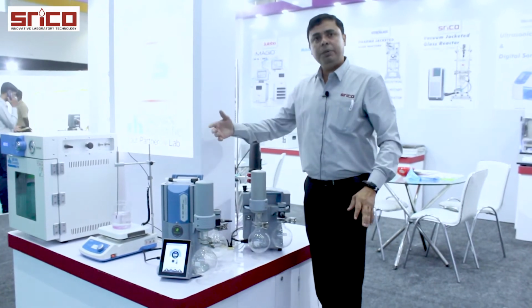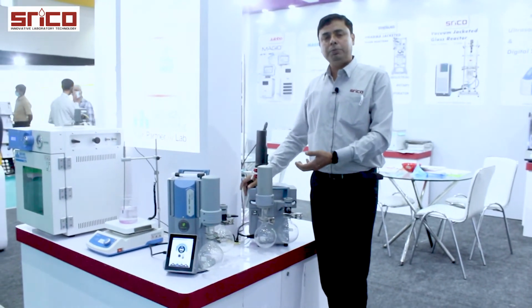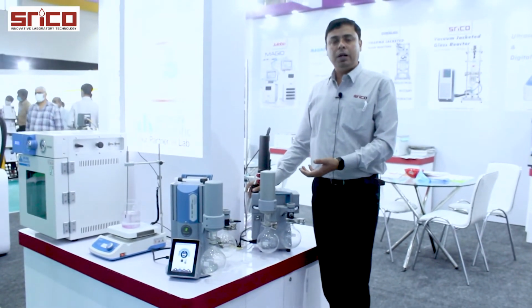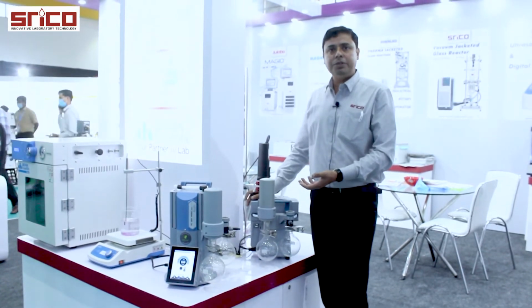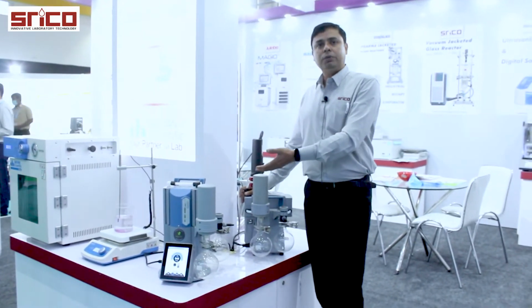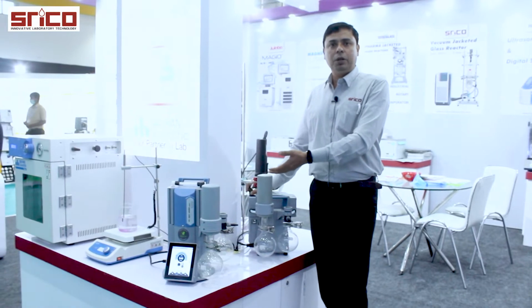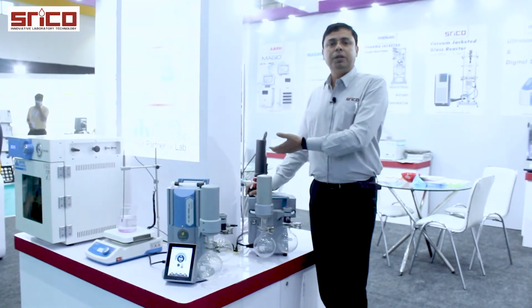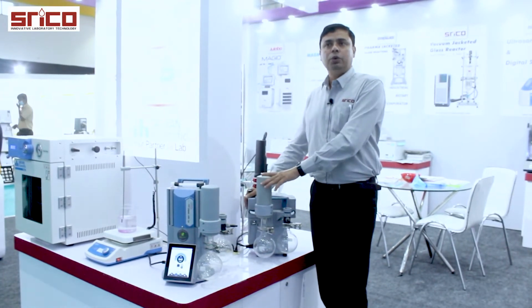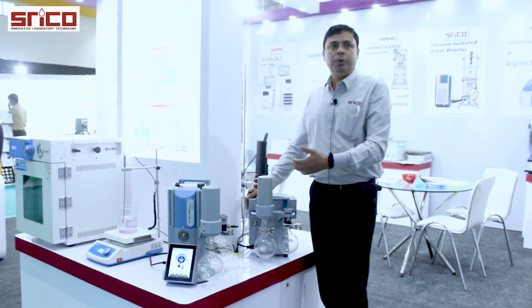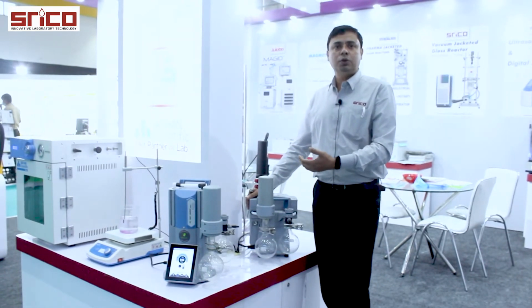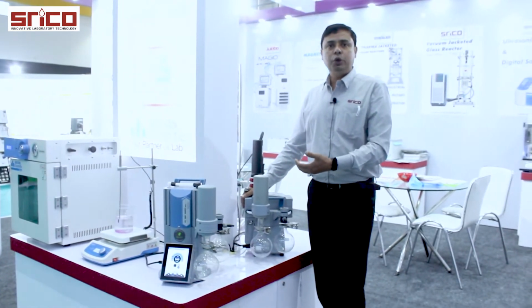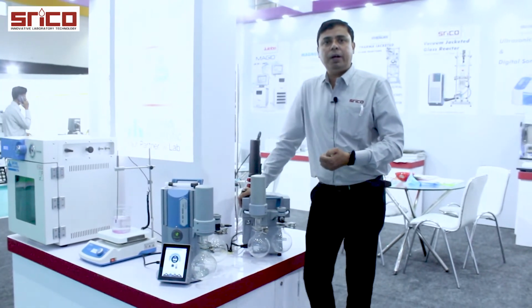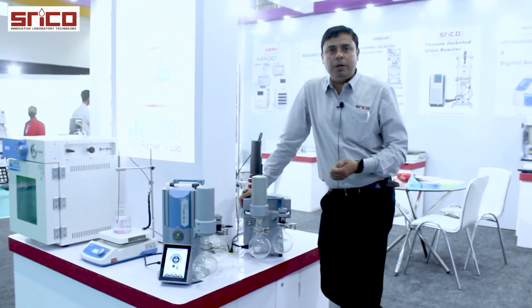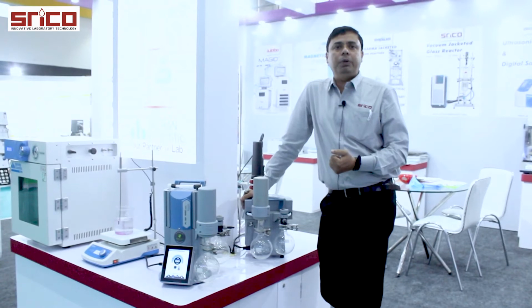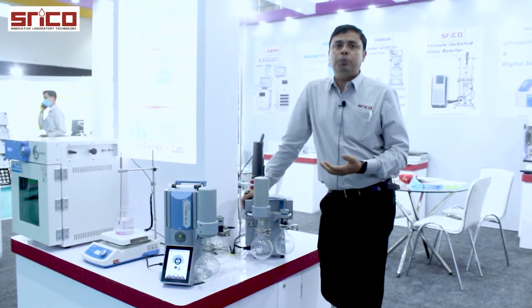And we have different models starting from small pumps which can give 70 millibar or 100 millibar for filtration application, and these models can be used for small distillation application, a rotary evaporator. We have bigger sizes, and this company is also giving a high vacuum pump, oil-free vacuum pump based on scroll type, that is Vacuubrand Pure 10C, which can give vacuum up to 10 to the -2 level with a very high pumping speed of 9 meter cube per hour.